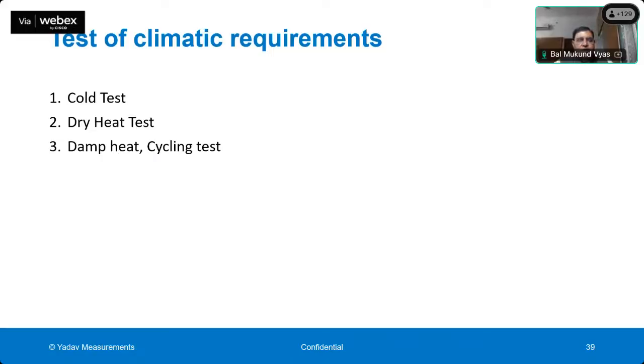Another test which the meter has to pass through is the climatic requirement. As I was telling, the meter can face very high temperature, and it can face very low temperature. We have to ensure that the meter's functionality and its accuracy are not affected because of this temperature, and also the humidity condition.